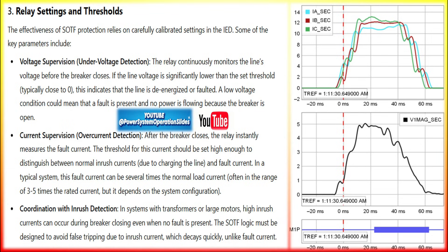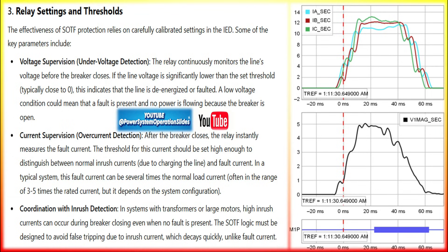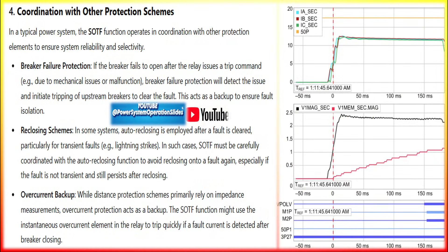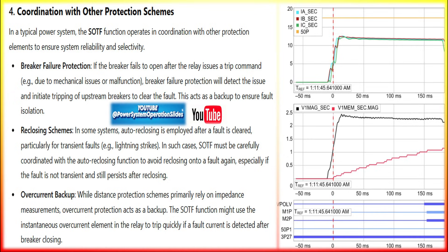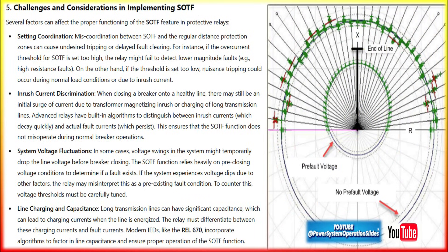The SOTF function can involve multiple protection elements, including distance protection elements. Normally, distance relays divide the line into protection zones; however, during an SOTF condition, the relay doesn't rely on the conventional zone-based tripping mechanism. It may use Zone 1 immediate tripping or even an overcurrent element. The SOTF function may also utilize overcurrent relay elements — instantaneous or definite time — to trigger faster tripping. Additionally, voltage supervision uses a sudden drop in voltage or low voltage before closing as another indication of faulted conditions, helping to differentiate between faulted and healthy conditions.